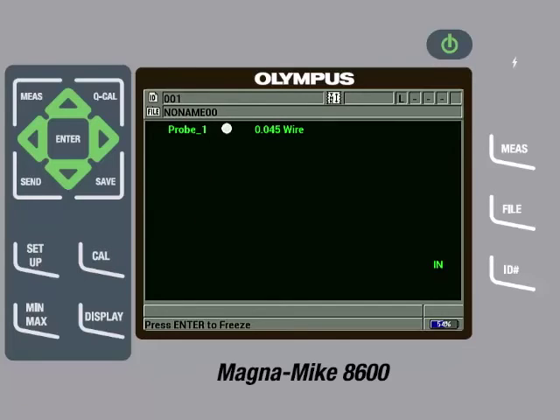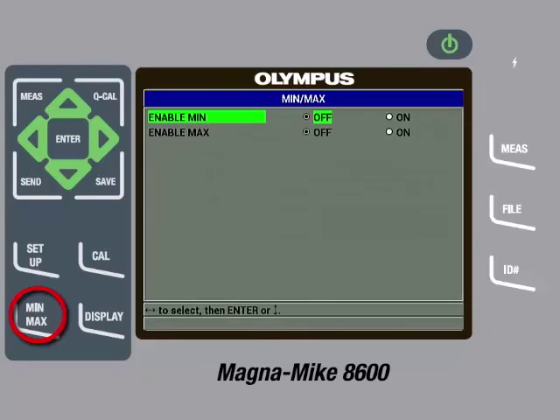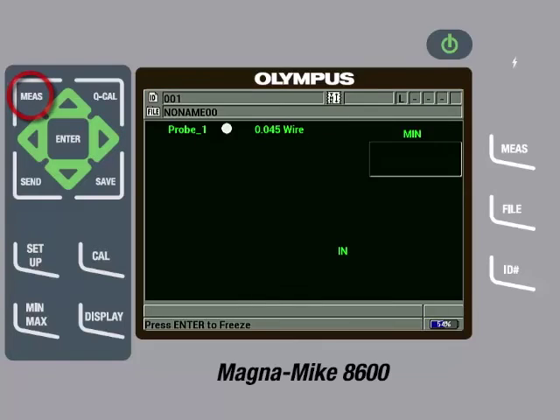on the actual part. The true thickness will be when the target is directly over the center of the probe tip, which also corresponds to the minimum thickness measurement. The gauge will read a thicker measurement when the part is misaligned. For this reason, it is recommended to enable the minimum capture feature. To do this, we will press the minimum-maximum key and then enable minimum to on by pressing the right arrow. We can then press the Measure key to return to the main measurement screen.